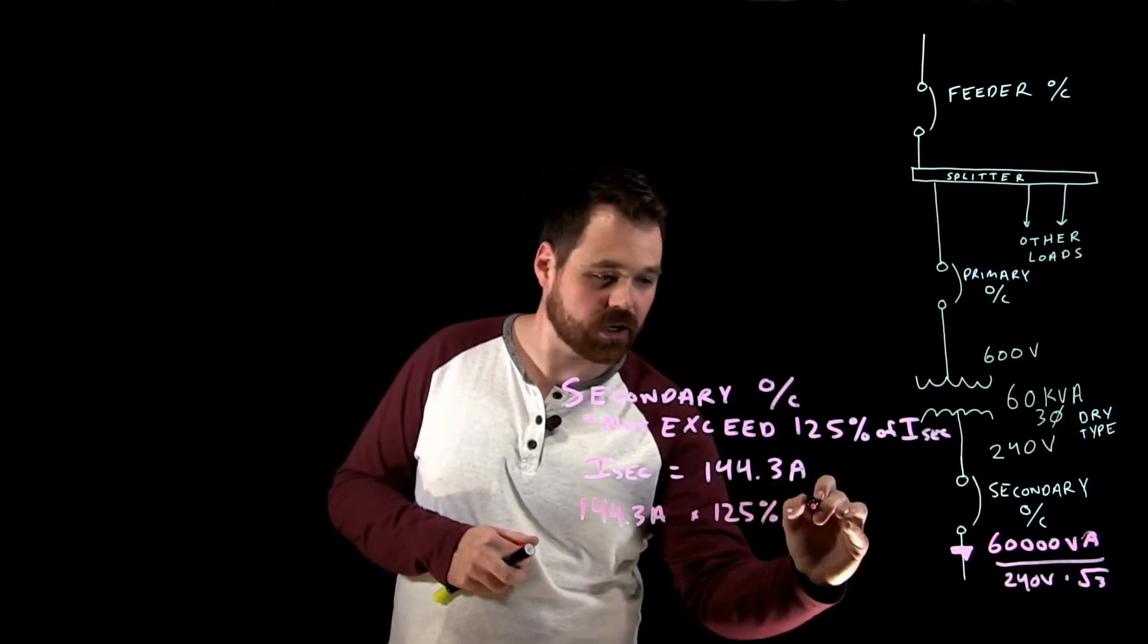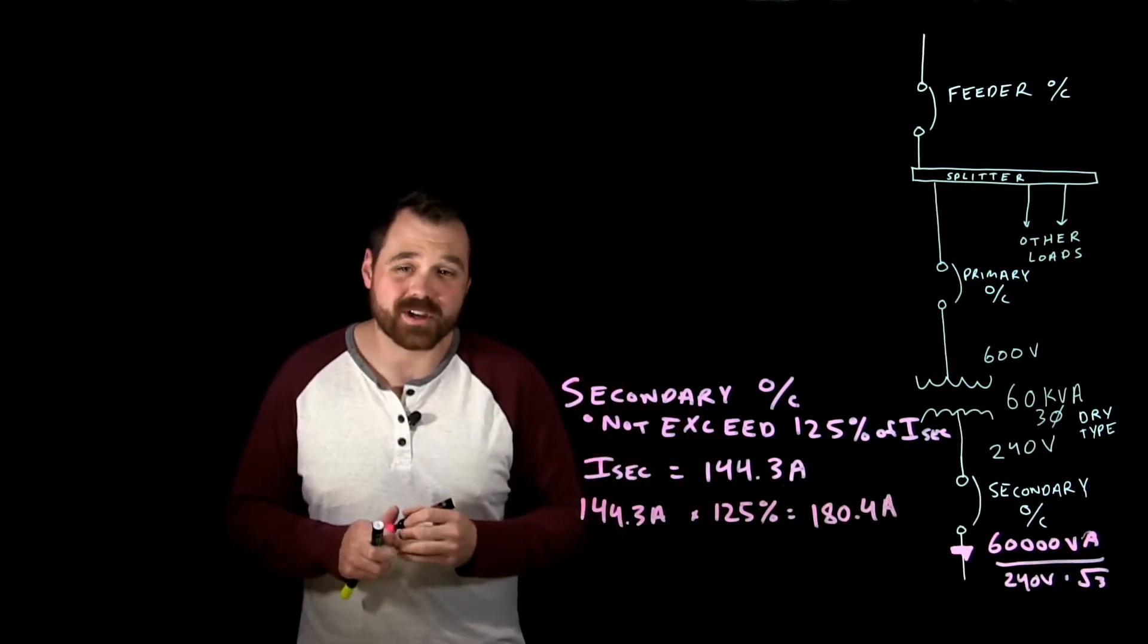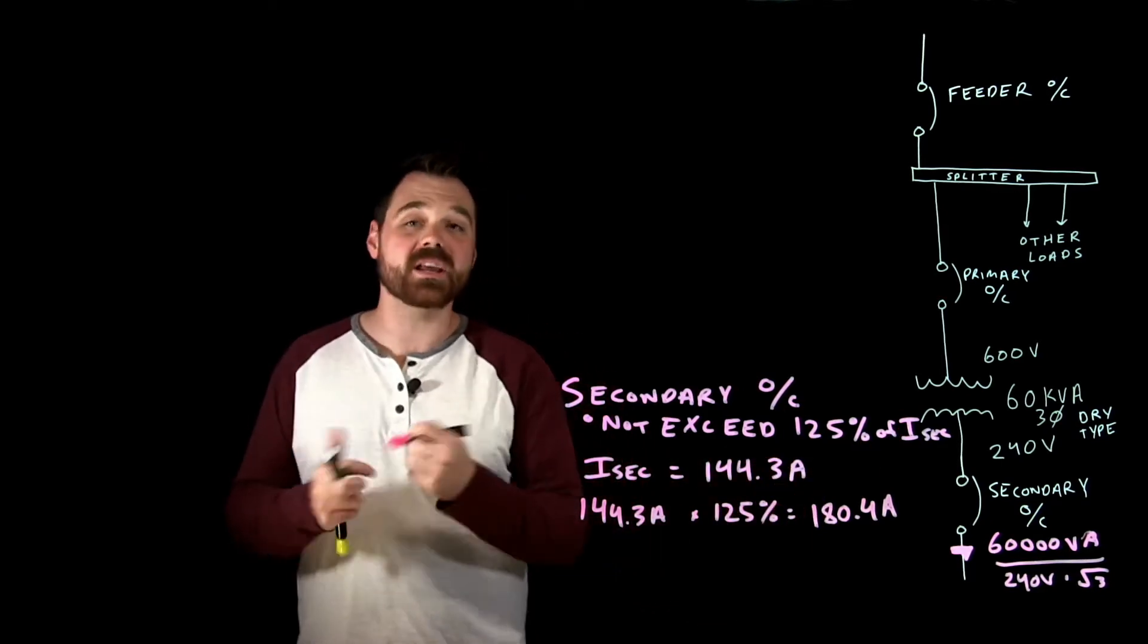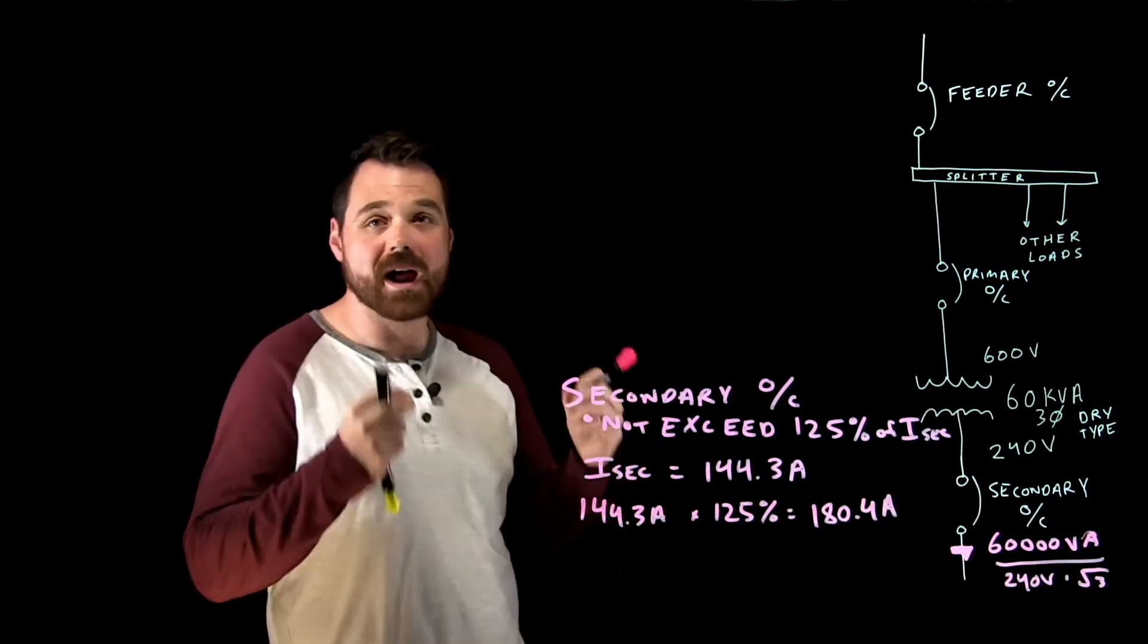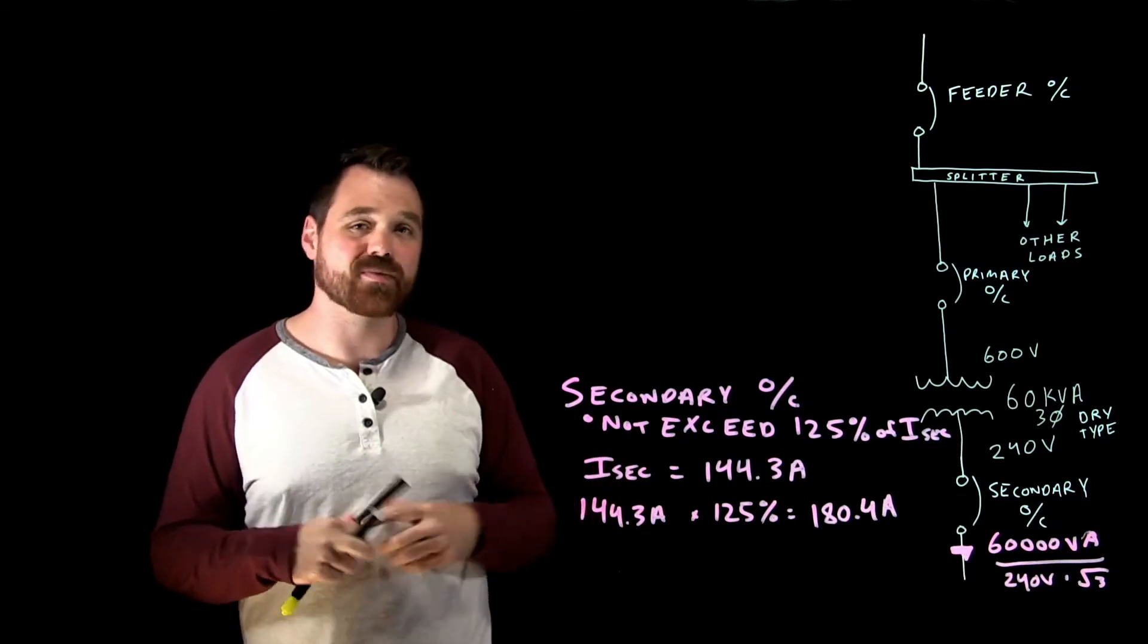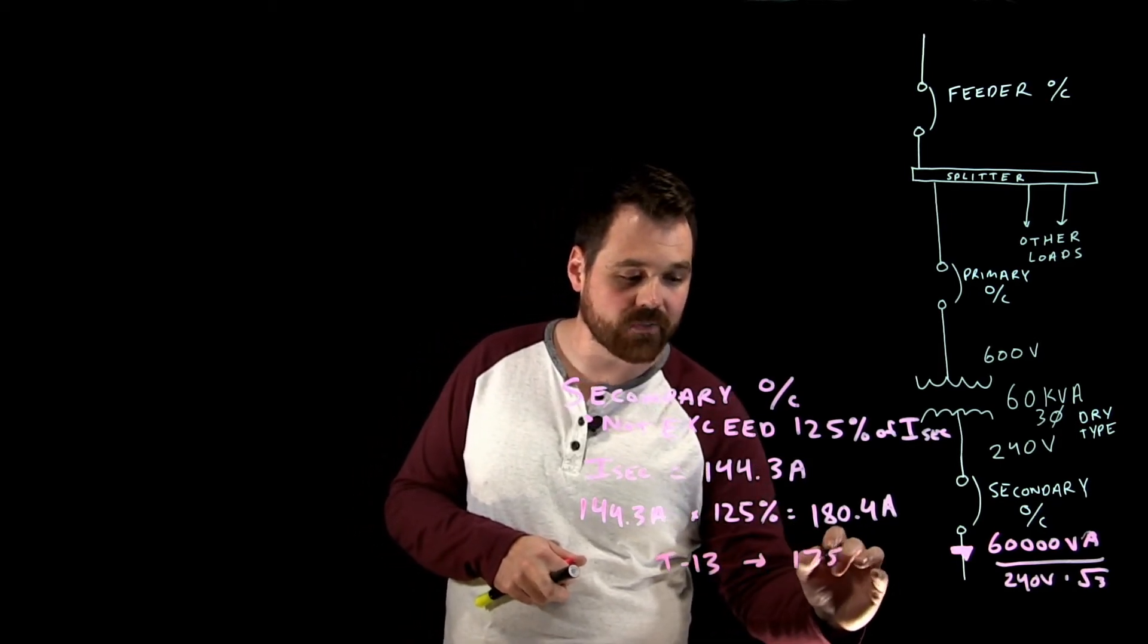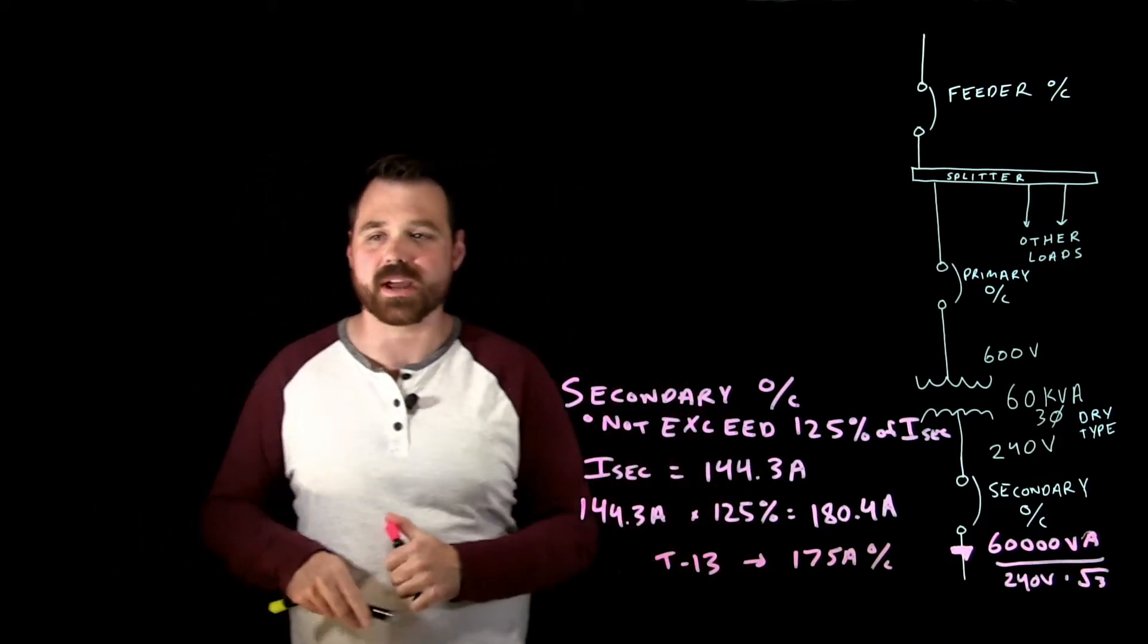Now the trick here is the wording. It says the overcurrent device shall not exceed 125 percent, meaning if I go to the store and there's not a 180.4 amp overcurrent device available I have to go to a smaller size. So if you're using based off of table 13 this would mean I would be in a 175 amp overcurrent device.